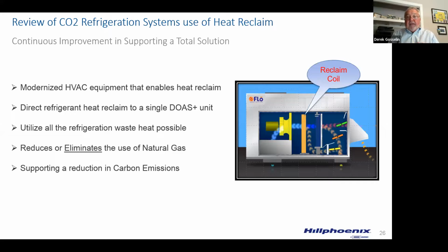We're not losing anything, transforming it into glycol in a two-stage system. This also allows us, by better utilizing this heat, to reduce or even in some cases eliminate the use of natural gas in heating your store. If your system is large enough and gives off enough heat, you can heat your store by directly feeding it into your HVAC system. That reduces the use of natural gas, which provides both energy efficiency and carbon reduction.